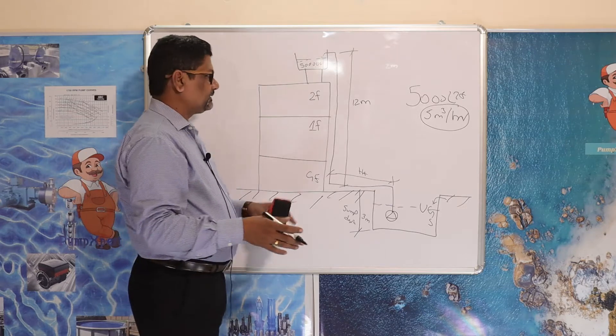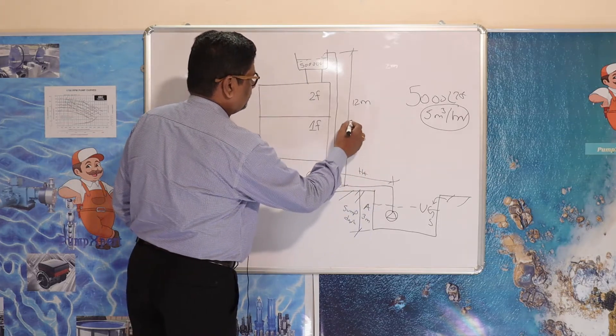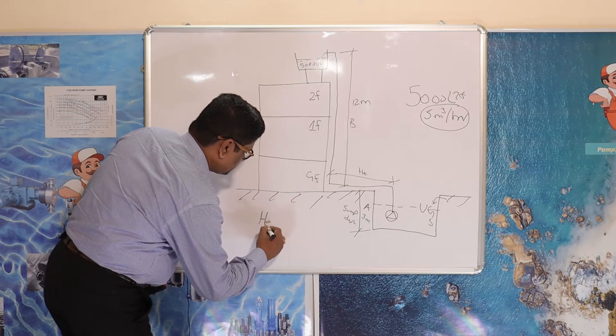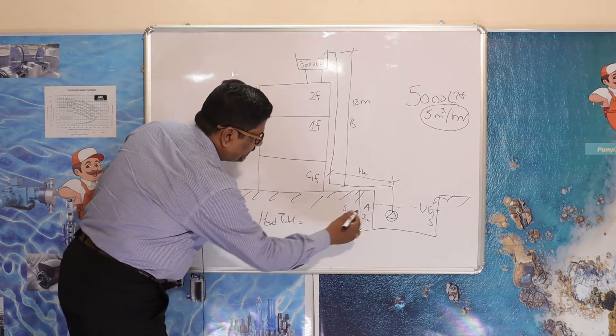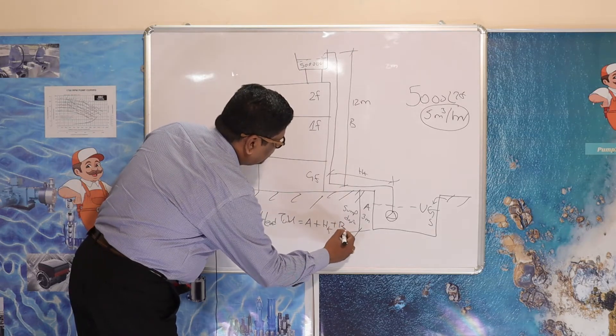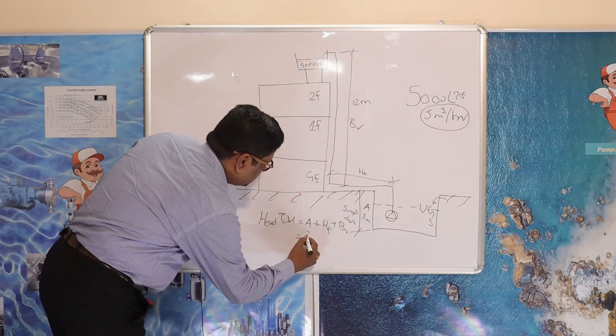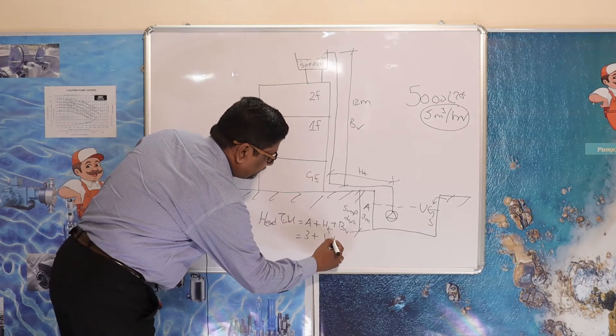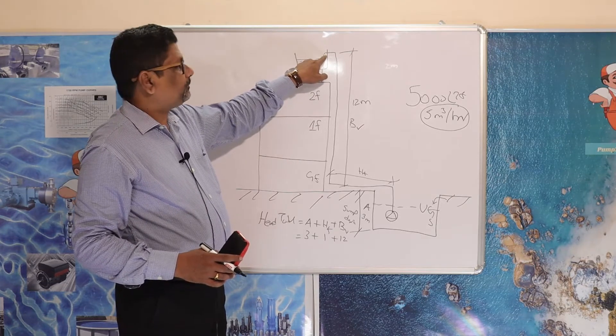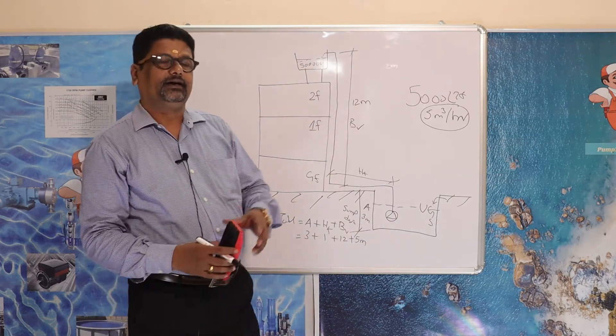So I call the sump depth A, the horizontal friction loss HF, and the vertical height B. My total head equals A plus the friction loss on the horizontal line plus the vertical height. I also need to consider the pressure required at the delivery point — I will take it as 5 metres, which is 0.5 bar minimum required.